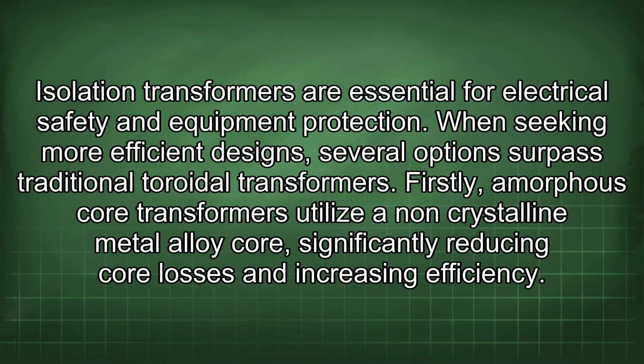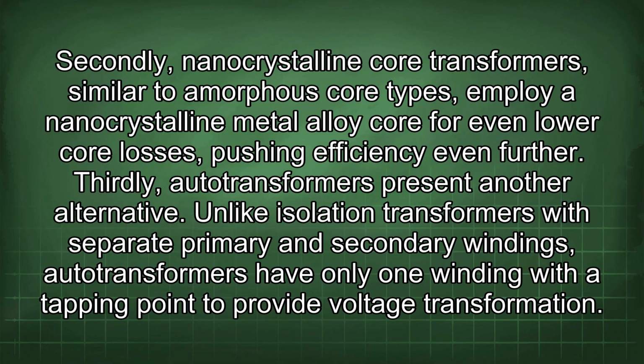Isolation transformers are essential for electrical safety and equipment protection. When seeking more efficient designs, several options surpass traditional toroidal transformers. Firstly, amorphous core transformers utilize a non-crystalline metal alloy core, significantly reducing core losses and increasing efficiency. Secondly, nanocrystalline core transformers, similar to amorphous core types, employ a nanocrystalline metal alloy core for even lower core losses, pushing efficiency even further. Thirdly, autotransformers present another alternative.